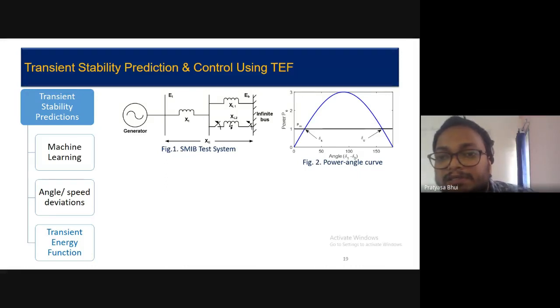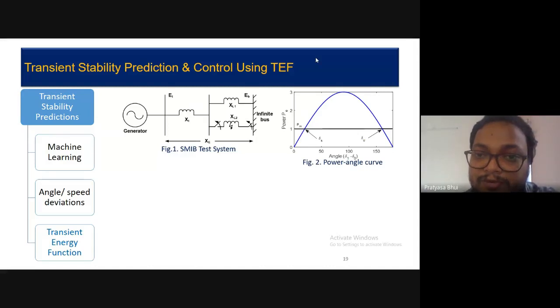So you can see here that this is a P-delta curve of a single machine infinite bus. The stable equilibrium point is delta S, and the unstable equilibrium point is delta U. Now, how do you calculate delta U? That is 180 degrees minus delta S. If we consider the infinite bus also as a generator, then the angle of the infinite bus is 0 for the stable equilibrium point, and it is 0 for the unstable equilibrium point as well. So if we talk about both the generator angles, here it is 0 comma delta S, and here it is 0 comma delta U. Now here there is only one possibility, that this generator will become unstable.